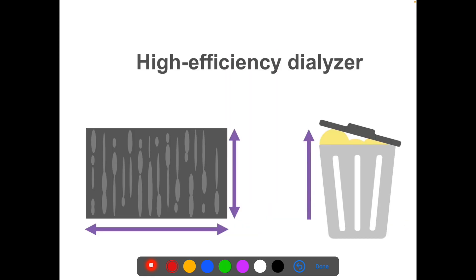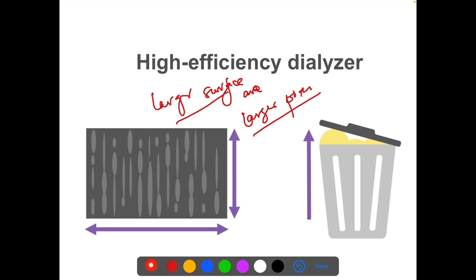High efficiency dialyser — that is high flux — is so called because it has a larger surface area and larger pores, providing more membrane area for diffusion and convection. Larger pores allow more convection and more diffusion. So larger surface area and larger pores make a dialyser high efficiency.